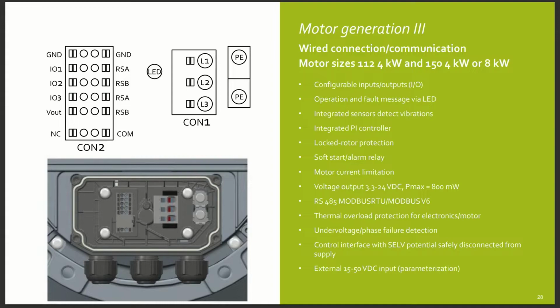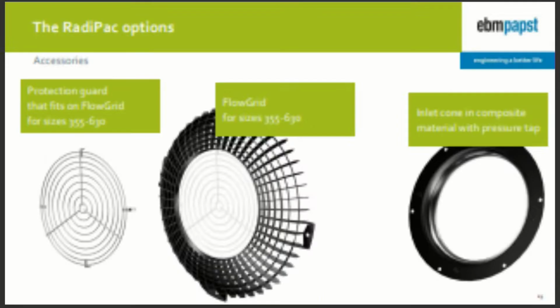And the electronics. Some of the features I mentioned already, but there are some others, like the integrated PI controller. We have locked rotor protection, over voltage detection, phase failure detection, and in the motors above, starting from 4 kilowatt power, we have integrated a sensor to detect vibrations. And later on I will tell you a little bit more about this feature.